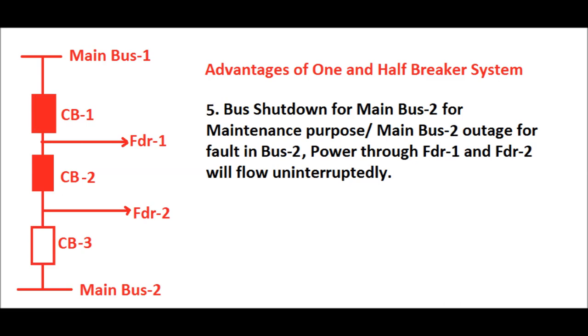Similarly, consider a bus shutdown for main bus 2 for maintenance, or an outage of main bus 2 due to a fault. Power through feeder 1 and feeder 2 can still flow uninterruptedly via main bus 1, with CB1 and CB2 in closed positions. Feeder 1 gets power through main bus 1 via CB1 in closed position, and feeder 2 gets power through main bus 1 via CB1 and the tie CB in closed positions.